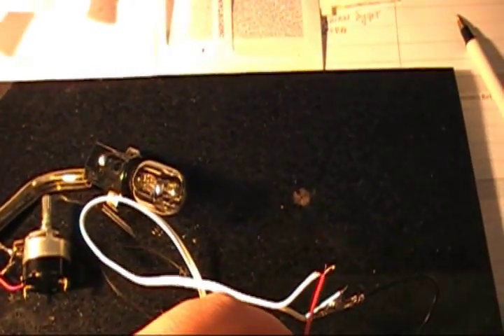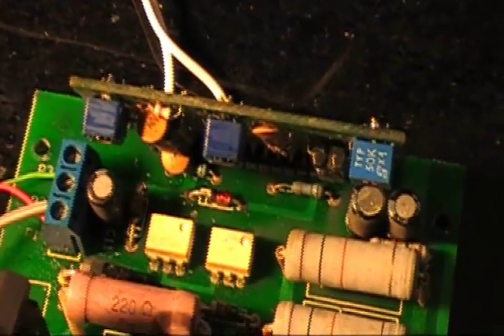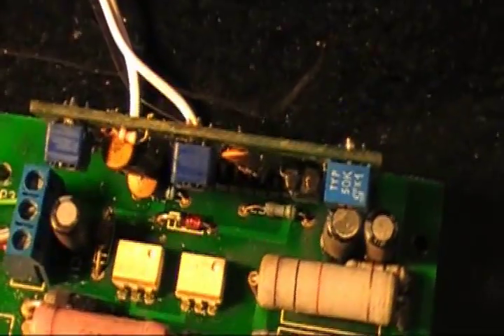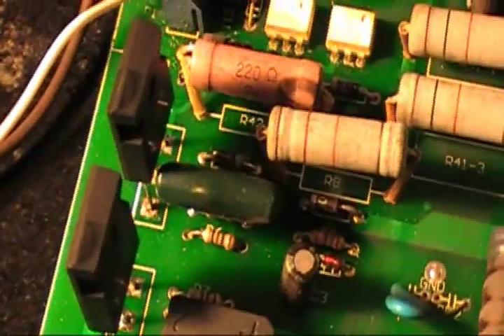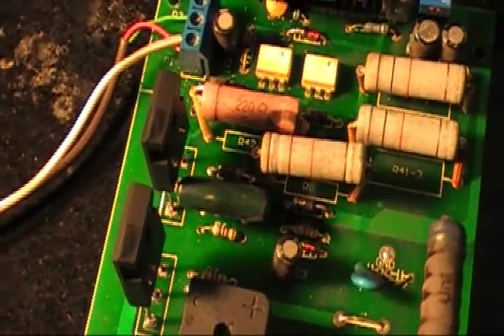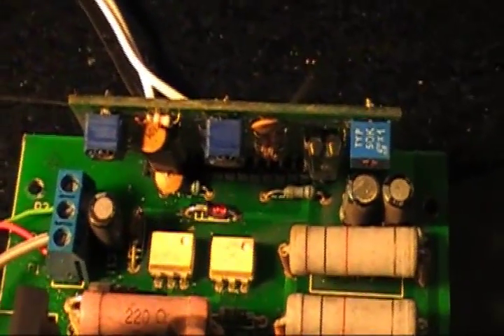That tells us there is something wrong with the digital controller board. The digital controller board is the first stage of our board — before the opto-coupler. This is the main part in the board that we cannot replace because we cannot find parts for it. So we've verified that the power module — the MOSFET transistors — is working, we've verified that the opto-couplers work, and we've verified that the signal from the digital controller board does not travel to the opto-coupler.